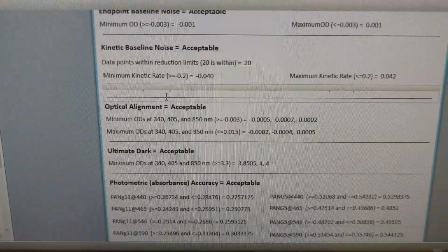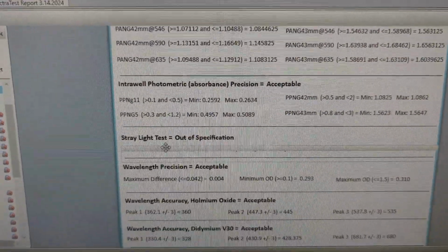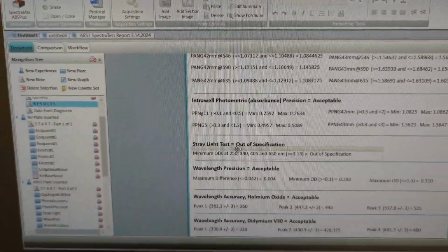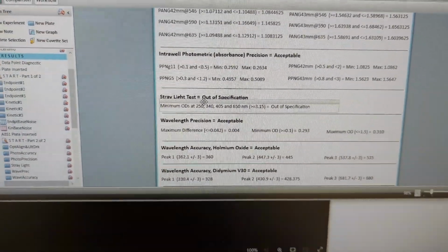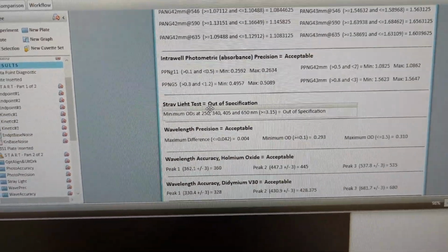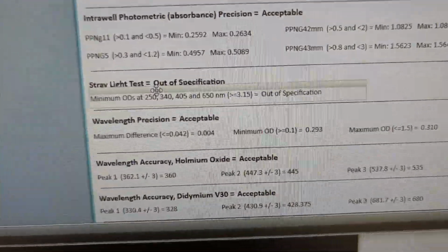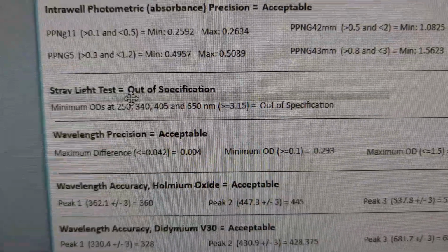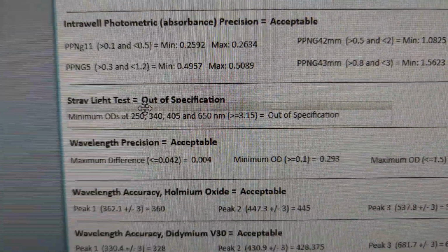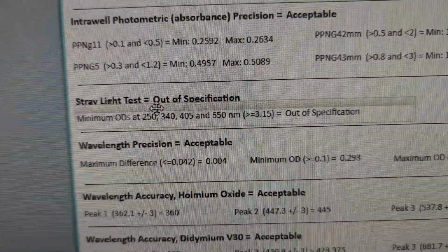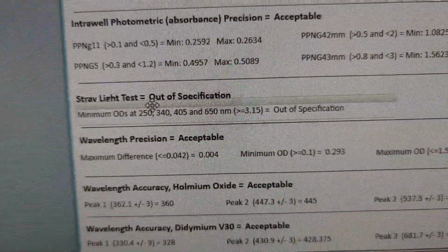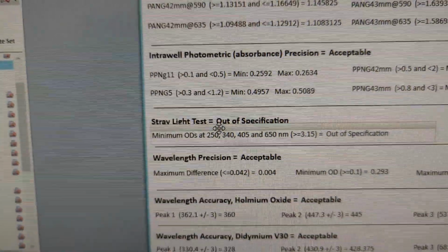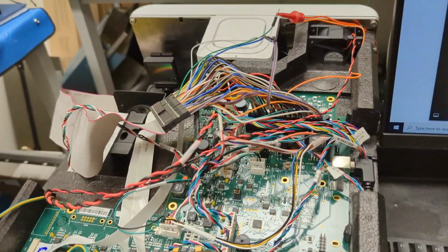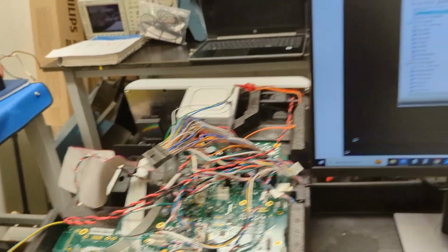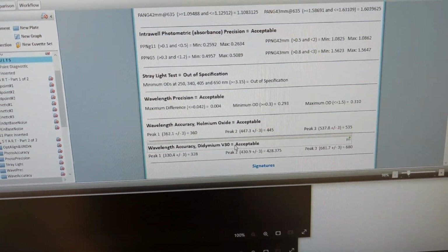Everything is passing with one exception. It did fail just barely for stray light. There's a standard for stray light in each of A, B, C, D, E, F, G, H. There's one standard for each. Well, it failed at 250 nanometers. The acceptance criteria is greater than or equal to 3.15. It's 3.149, which kind of sucks because if that's how many sig figs they give, well, 3.149 is really 3.15. But anyway, I think it failed just because this thing is still open and the cover's still off, and I'm pretty confident that once I put it back together and run it again, it will pass. All right? But as you can see, wavelength accuracy is acceptable, everything else is good.